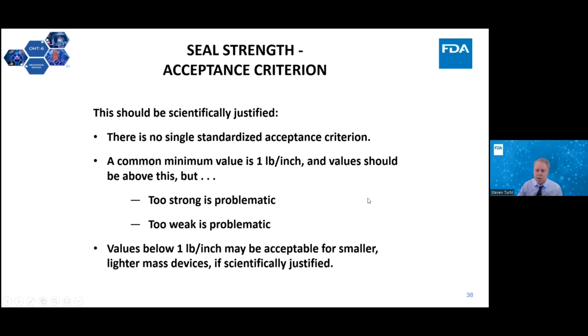Very common. If you go above this, if it's too strong, it's going to be problematic because it's going to take a lot of force. And whoever's trying to open that package is going to be pulling on the package and the product can go flying across the room. You don't want that. If it's too weak, that's also going to be problematic. You're going to have a shaky package. It's not going to be holding together very well. Values below 1 pound per inch may be acceptable, and we do see this quite commonly for smaller, lighter mass devices if scientifically justified. So if you have a very light, small product, designing a package with a seal strength lower than 1 pound is okay, but again, has to be scientifically justified.